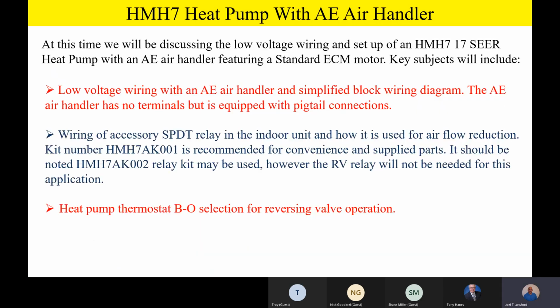Hey team, at this time we're going to be discussing low voltage wiring and the setup of the HMH7 heat pump. And we're going to start out with an AE air handler, which features just a standard ECM motor. Now, anytime we see in our Johnson Controls literature standard ECM motor, that's the old X13 type of motor that we call a standard ECM motor. It's been enhanced over the old X13 motors. They're a lot more reliable than they used to be. And these are the high efficiency motors that have the speed taps on them. They'll have typically 5 speed taps, 1, 2, 3, 4, 5. So that's the motor that we're talking about.